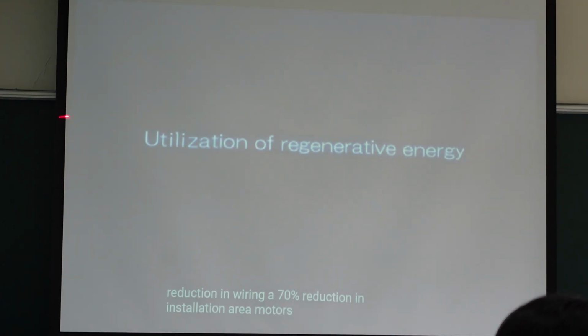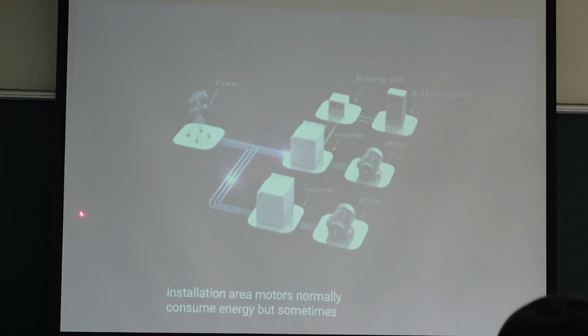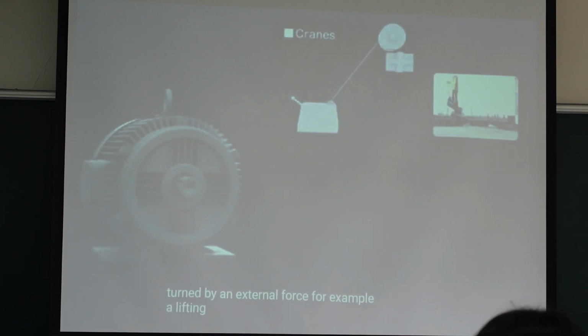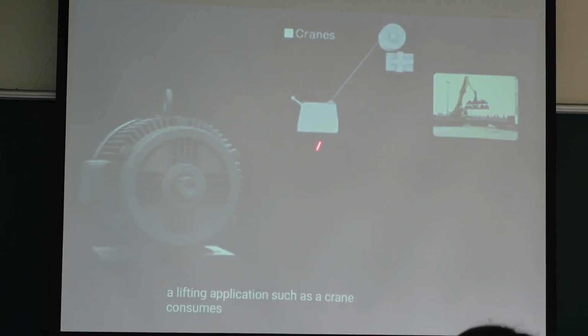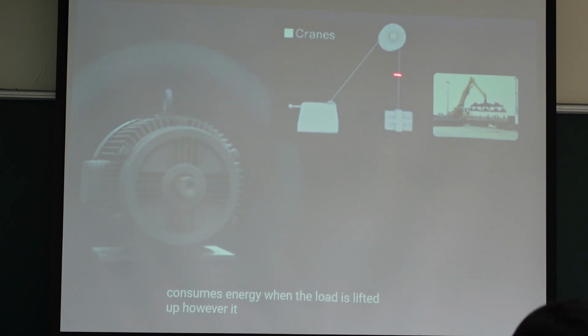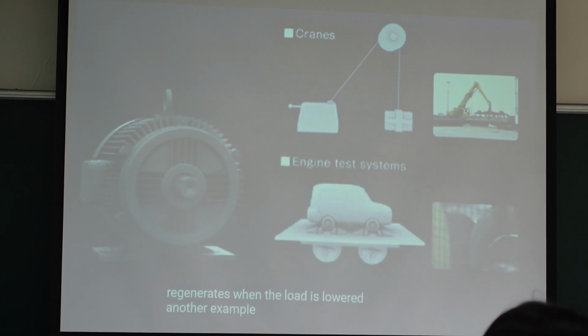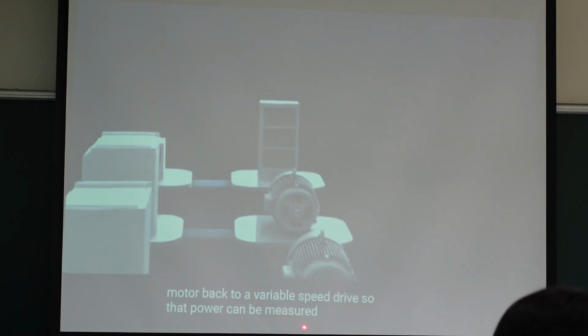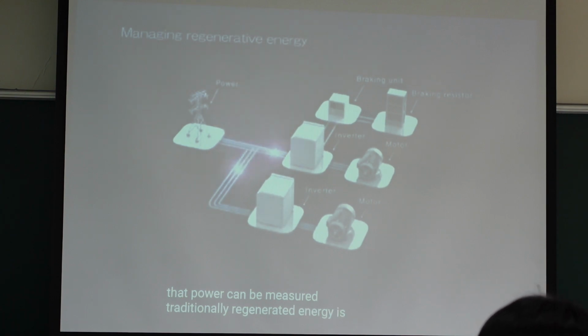So now we need bidirectional. Motors normally consume energy, but sometimes energy goes backwards when the motor shaft is turned by an external force. For example, a lifting application such as a crane consumes energy when the load is lifted up. So we need to regenerate energy when the load is lowered. Another example is a dynamo. We can regenerate and return energy back to the power company, delivered back through a variable speed drive so that power can be measured. Generated energy can be returned to the grid instead of wasted as heat in a braking resistor.